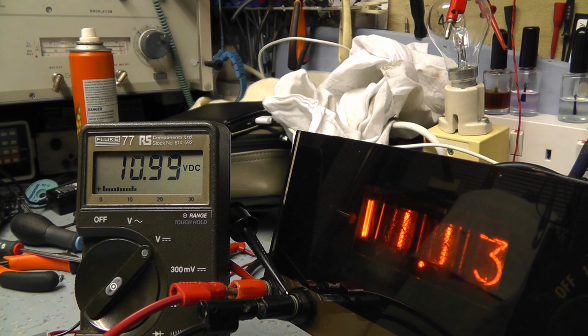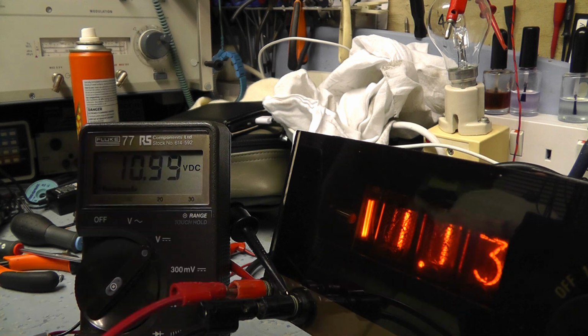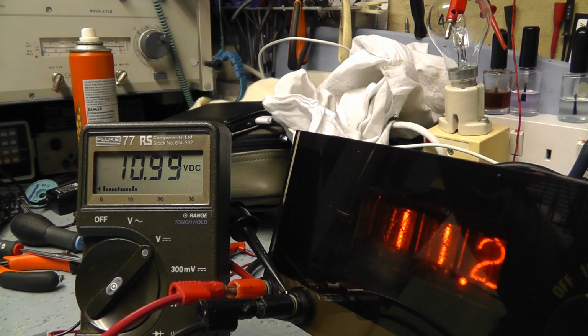Now that's a calibration error, and I can bring that in easily on the Roband meter, because there's an adjustment on the side which is just the multiplier. So what you do is start with the base voltages, which is the low end range, get that accurate, get the balance right, and then as you work up the ranges you adjust the pots on the attenuator. Okay, so we're a little bit out there. It should be 11 volts. We've got 11.13, but the offset should be good. Yeah, that's pretty good. Okay, so we'll go to 150 volts and just see what that's like.